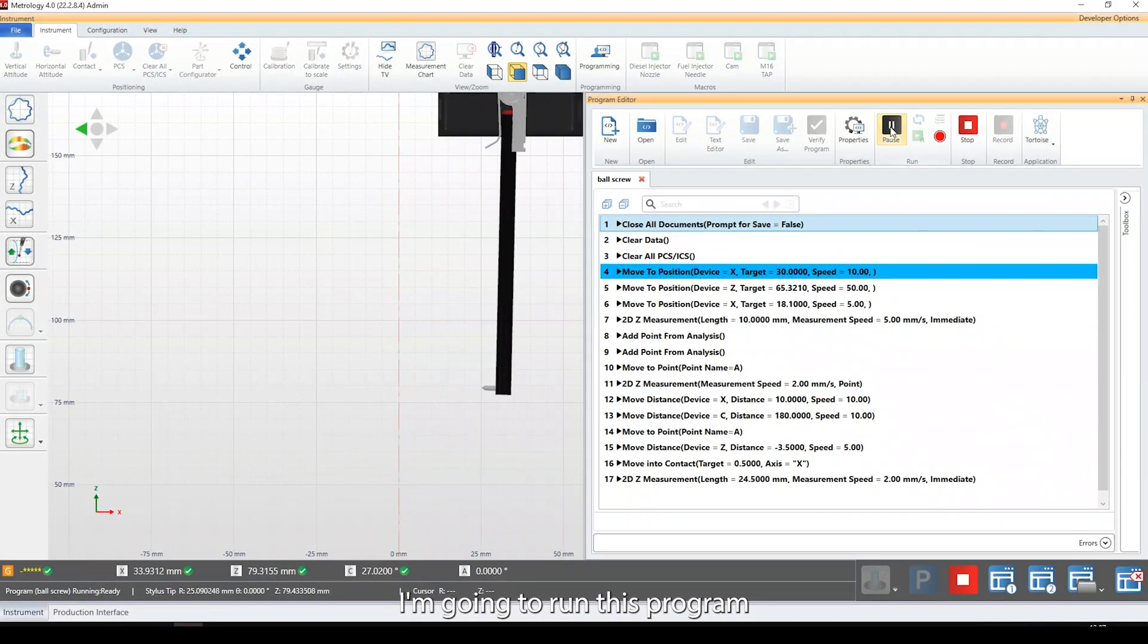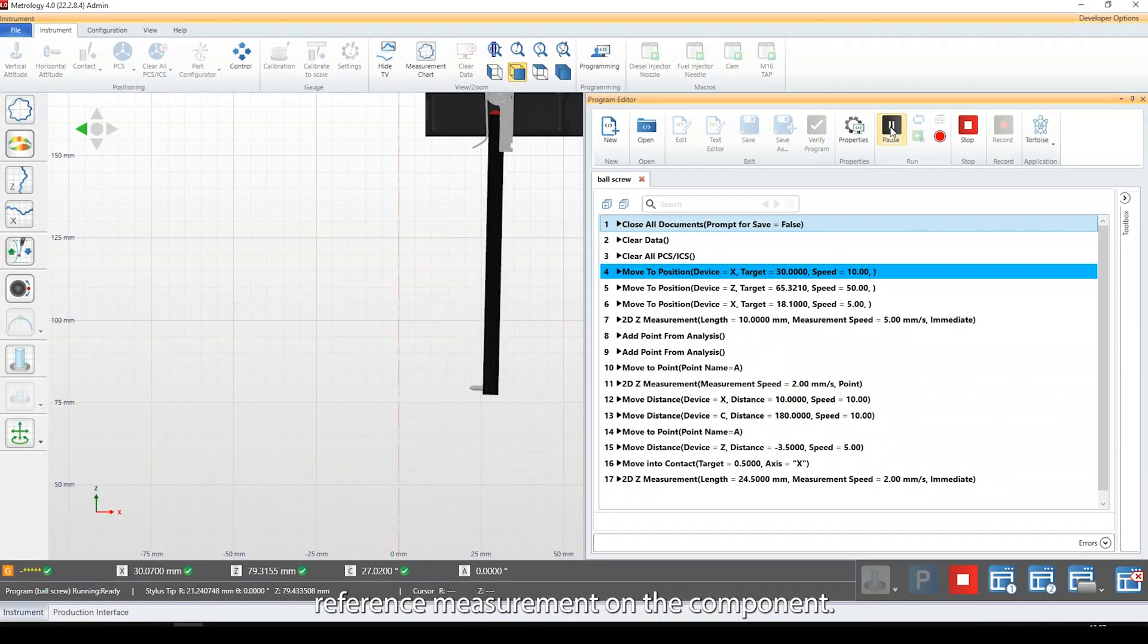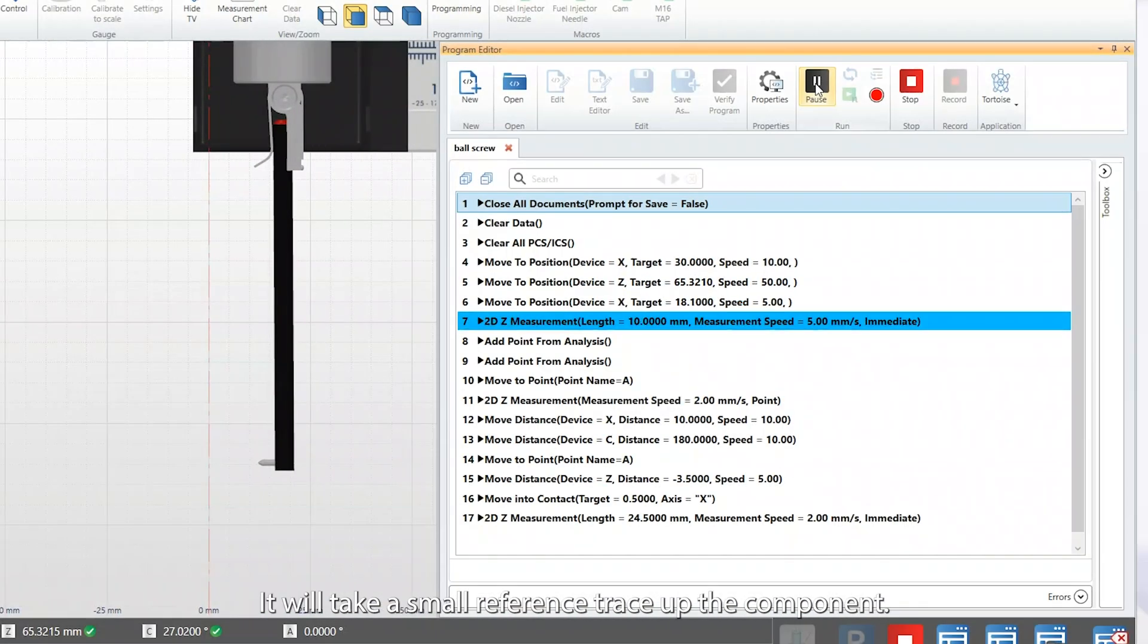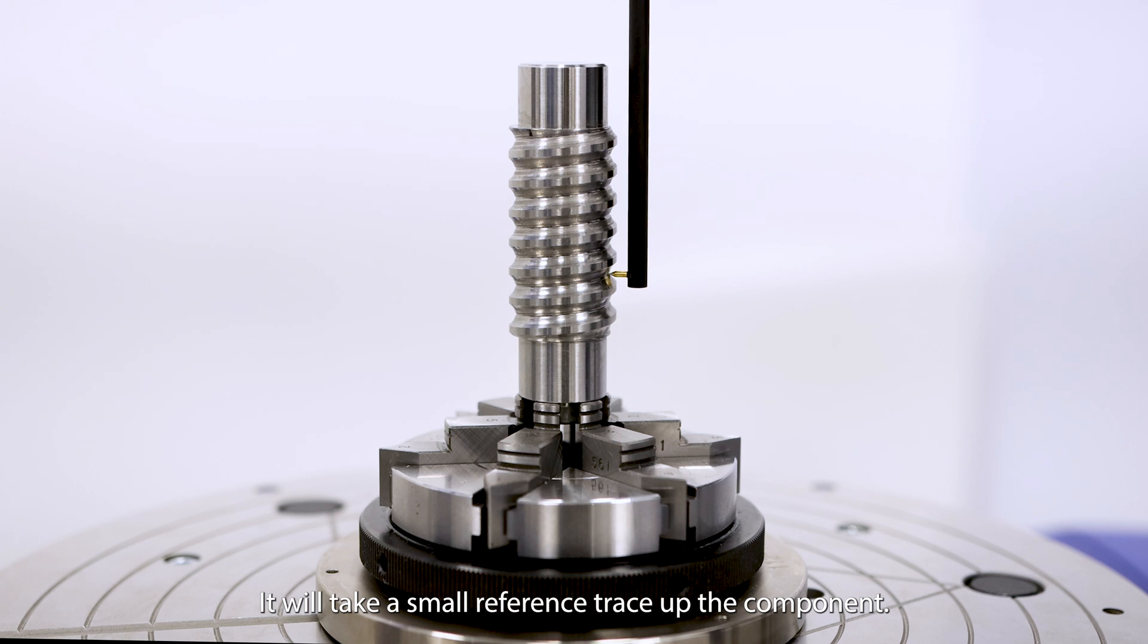I'm going to run this program and we're going to take the first reference measurement on the component. The stylus will contact onto the reference position and take a small reference trace up the component.